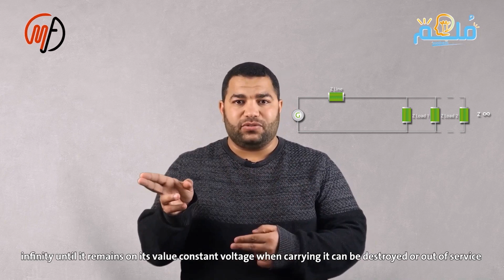We must understand the location of the fault is the first factor affecting the value of the fault current. Clearly, the further the fault is from the relay, the greater the resistance the relay sees, and thus the lower the fault current value. In contrast, the closer the fault is to the relay, the lower the resistance the relay sees, increasing the fault current value. This is why detecting distant faults is hard. The current increase is slight and often unnoticed.